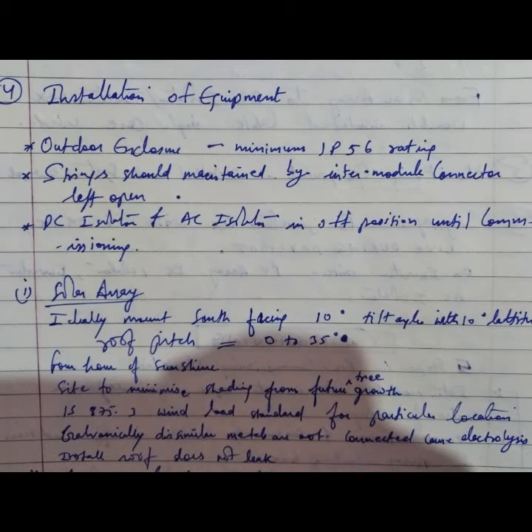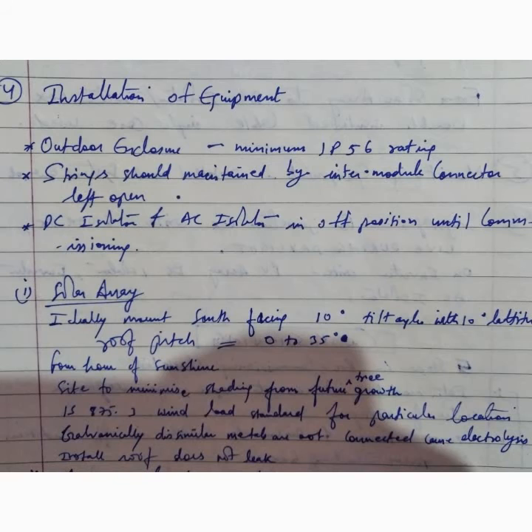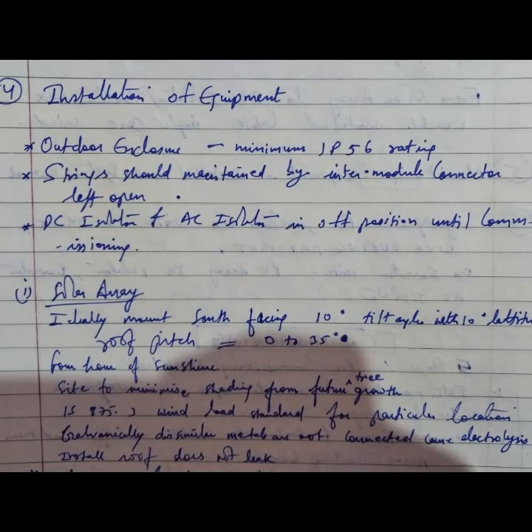Then the installation of equipment. Outdoor enclosure: minimum IP56 rating should be required. Strings should be maintained with the intermodule connector left open. The intermodule connector is MC4 connectors or some connectors between module and junction box, called intermodule connector. DC isolator and AC isolator should be in off condition until commissioning. Both are in off condition.